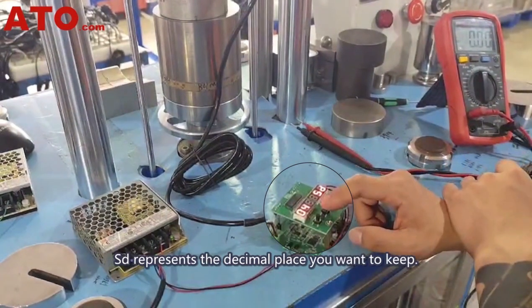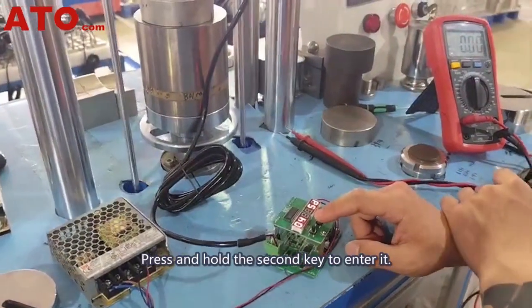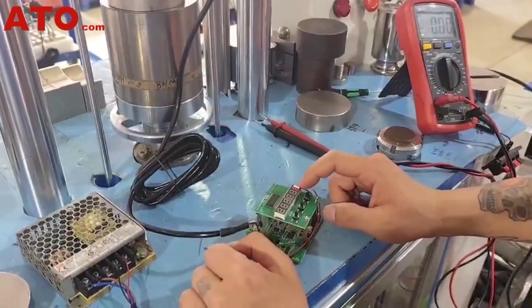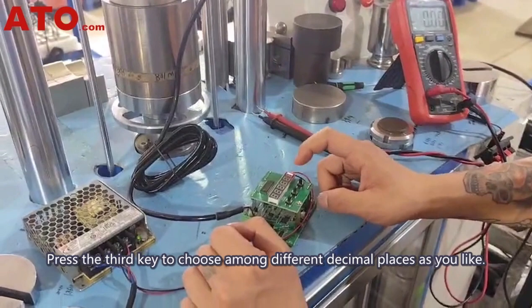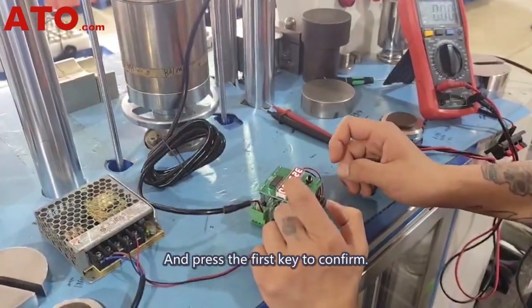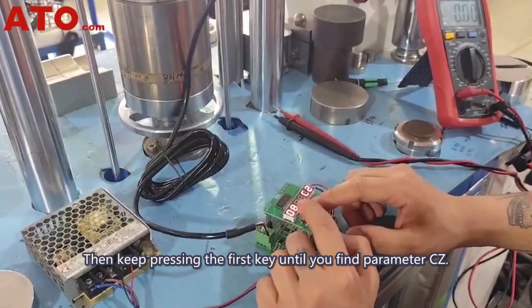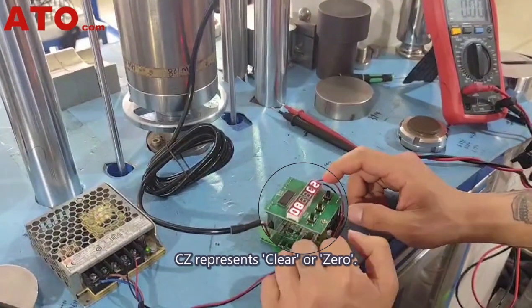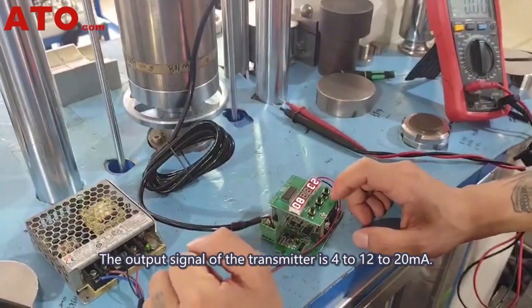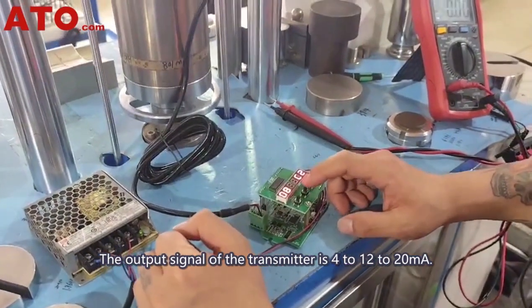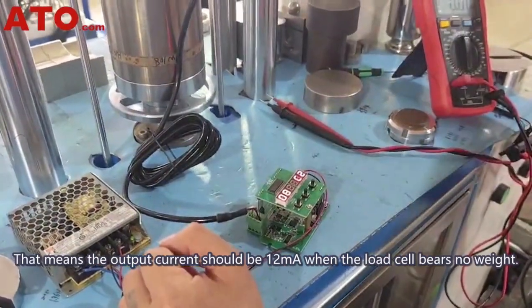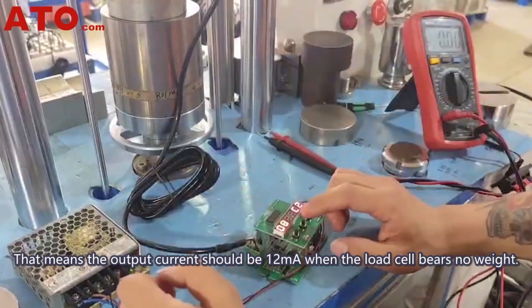SD represents the decimal place you want to keep. Press and hold the second key to enter it. Press the third key to choose among different decimal places as you like, and press the first key to confirm. Then keep pressing the first key until you find parameter CZ. CZ represents clear or zero. The output signal of the transmitter is 4 to 12 to 20 milliamps. That means the output current should be 12 milliamps when the load cell bears no weight.